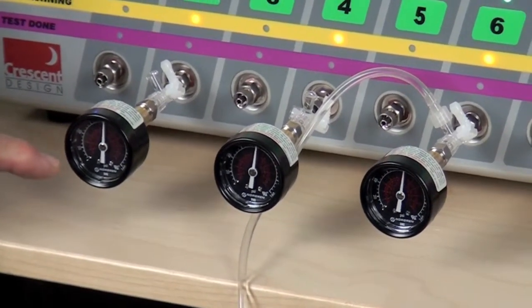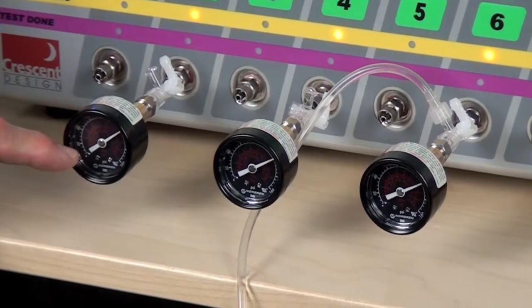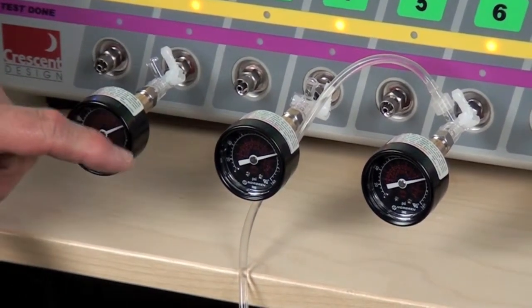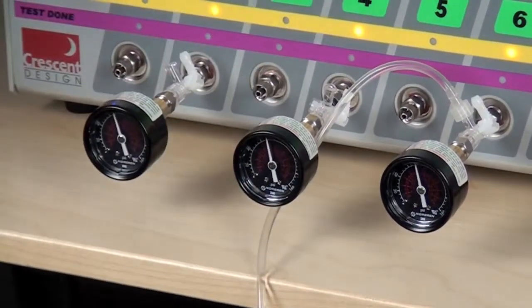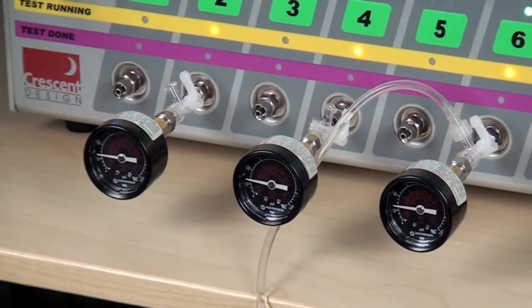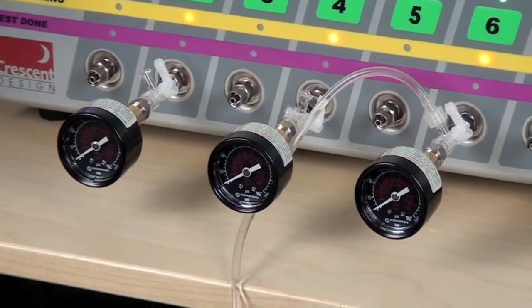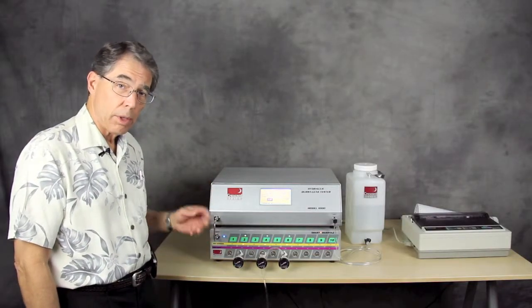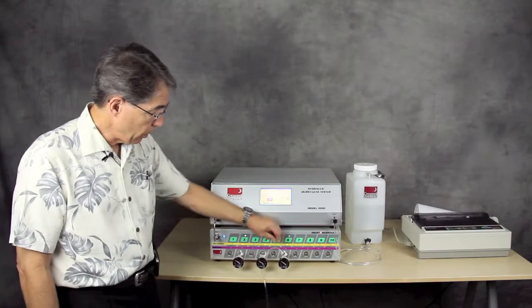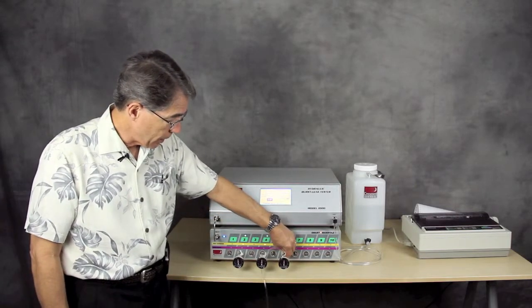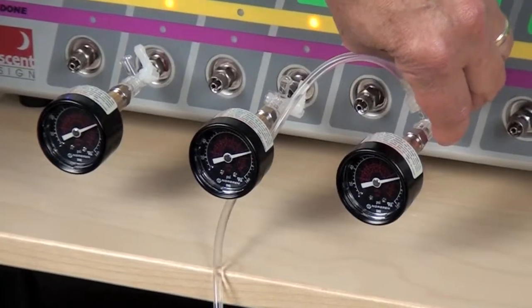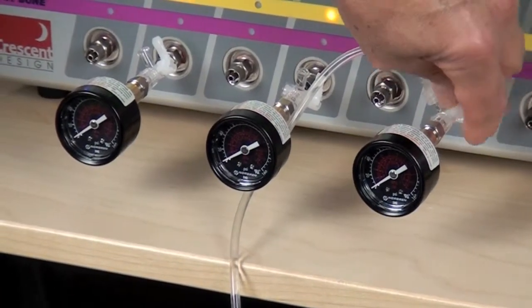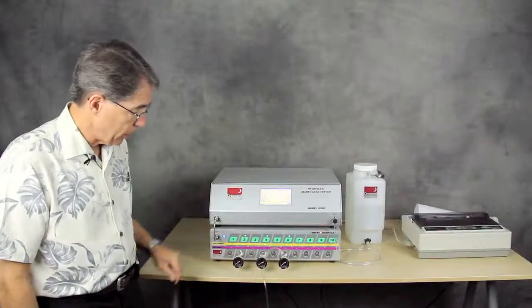So you notice the target was 120. And it got to 120. And now the gauges are going back down. This is a fatigue test. So it's just going to go up and down. It's three cycles. We're going back up to the target pressure now. And when we get to 120, I'm going to create a leak, which I've done right here by opening the stop cock.